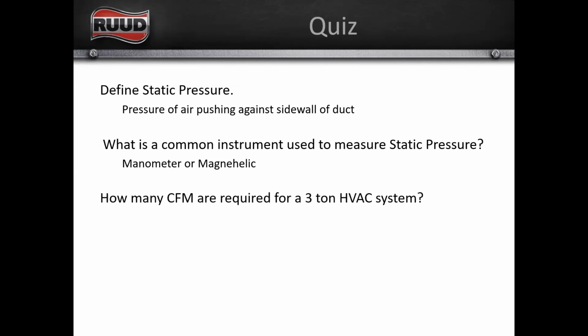But yep. How many CFM are required for a 3-ton HVAC system? So this might be a trick question. It is a trick question because I'm getting numbers here. Put your thinking caps on, guys. How do we know what the rated airflow is for indoor? In the condenser spec sheet. So he is correct. And finally, somebody else said depends on matchup, so that's good too. Another place, check the spec sheet for the outdoor unit or go to ahridirectory.org. All right, we couldn't fool everybody.